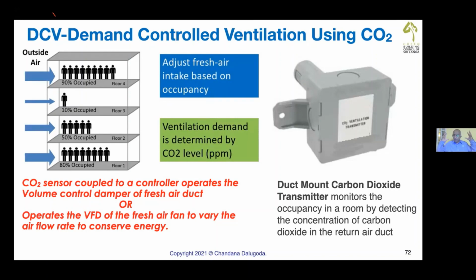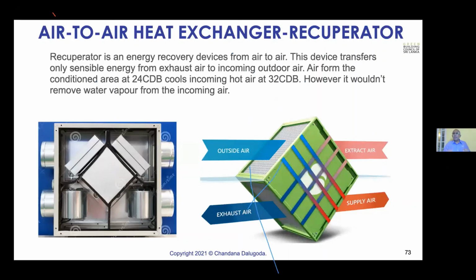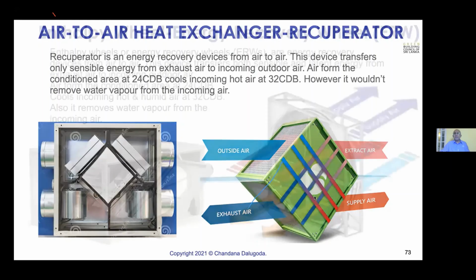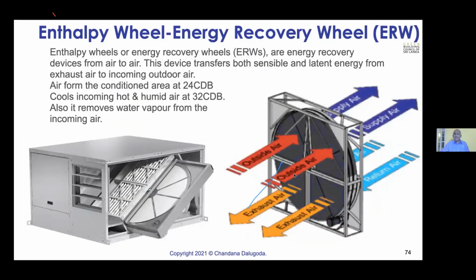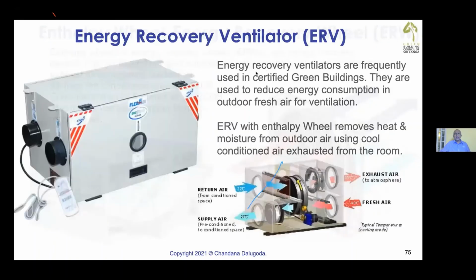Now, you are really compelled to provide outdoor air for occupant well-being. But outdoor air has a lot of energy problem. So you need to have an energy recovery system, an air-to-air heat exchanger, recuperator, like this. Or you have to use the energy recovery ventilator with an energy wheel, enthalpy wheel. What it does, the extract air from the office at 24 degrees C will cool incoming outdoor air at 32. Not even that, the enthalpy wheel will absorb water vapor. So moisture reduction, enthalpy reduction. So your power consumption drops.